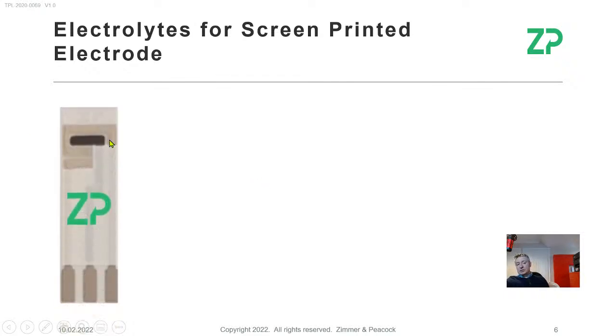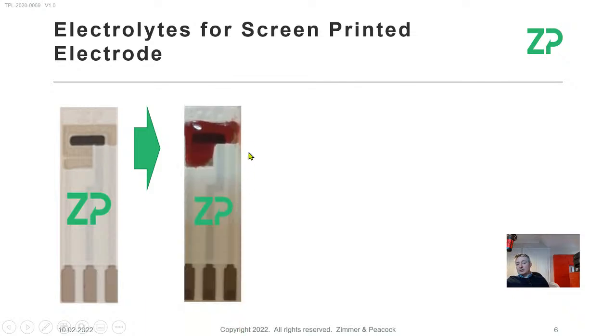And so this is a screen printed electrode. Onto it, you would put the sample. What's interesting about screen printed electrodes in the use of sensing or biosensing is there is no solvent. It's actually the sample that's the electrolyte. So here, the blood is essentially the liquid and the salts within the blood are the electrolytes. So when you ask the question in a screen printed electrode, what is the electrolyte? The answer is the sample is actually the liquid phase and the salts within the sample are the electrolyte.